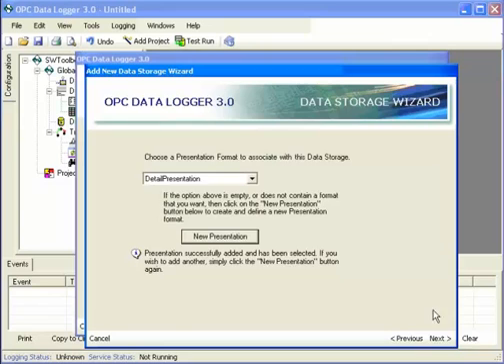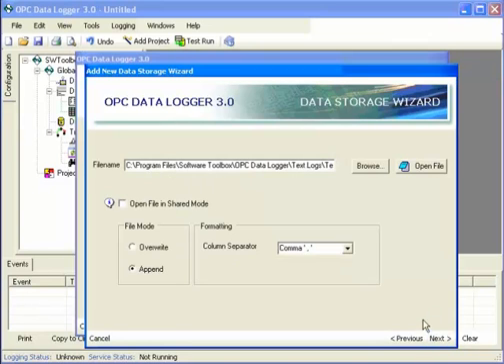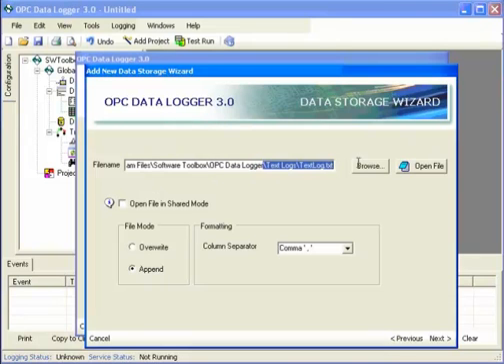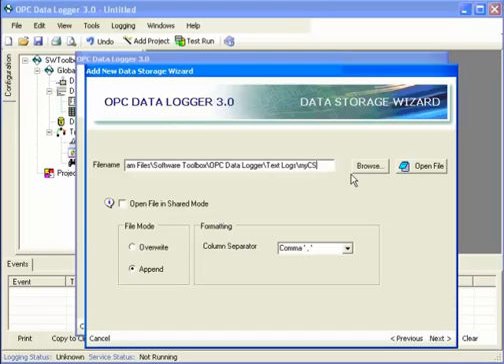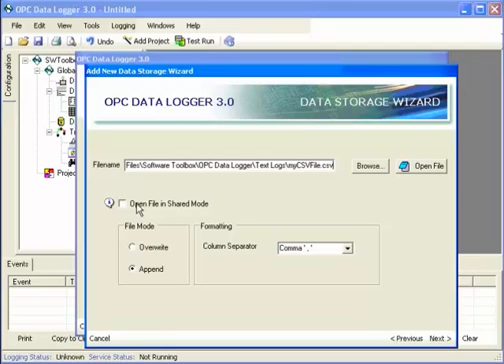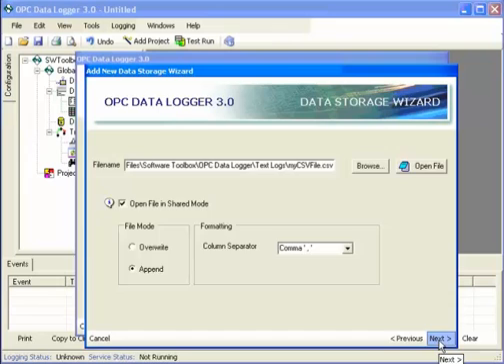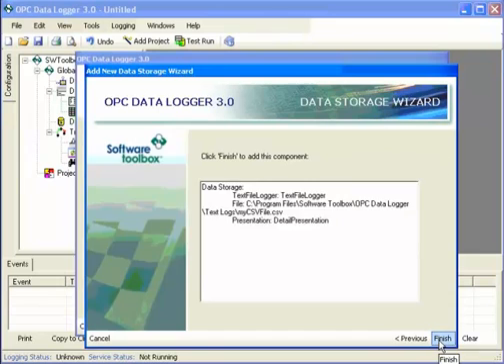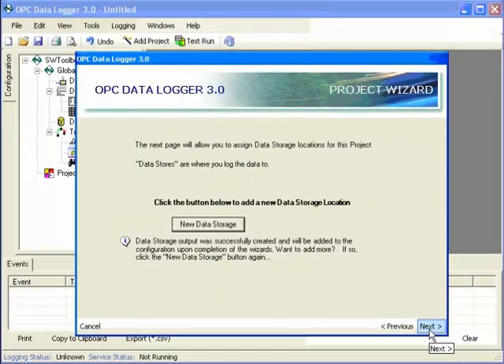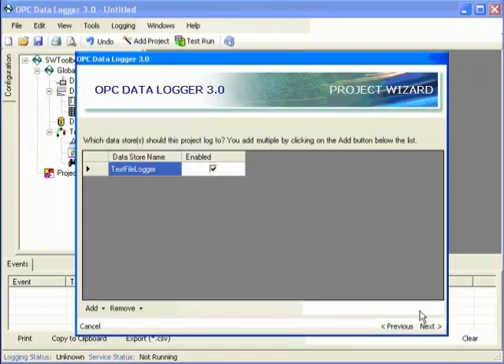And so that creates the presentation. It's automatically selected. Next, I need to configure the file information. I'm saving to a CSV, so I'm going to change the name of this to a CSV. I'm going to choose to open the file in share mode. What that means is that while data logger is still logging data, we'll be able to open the file in read-only mode. So that configures the storage.